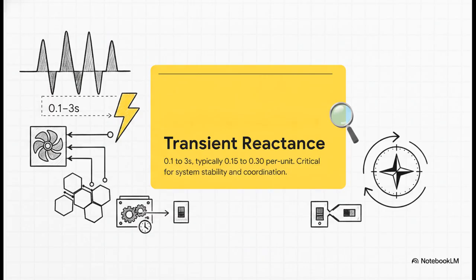Right after that initial explosion, the transient reactance takes over. This lasts from 0.1 up to about 3 seconds, and this reactance is slightly higher. This specific time frame is absolutely critical for system stability. It's what actually gives your protection relays those crucial milliseconds they need to detect the fault and coordinate trips, well before the generator falls completely out of synchronism.